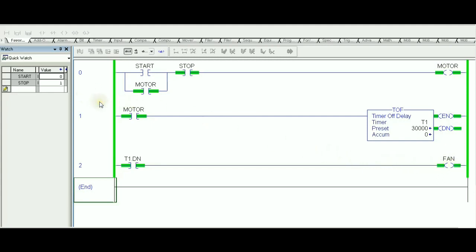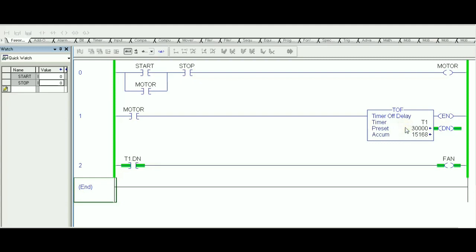Anytime you hit Stop, the motor immediately turns off because Stop is the only condition triggering it. However, when the motor is off, the XIC is false and the TOF actually starts timing from zero, aiming to reach 30 seconds. During those 30 seconds, the Done bit remains set, so the fan remains on even though the motor is off. Once the accumulator hits the preset value, the Done bit goes to zero and the fan turns off — that's the requirement fulfilled using TOF.